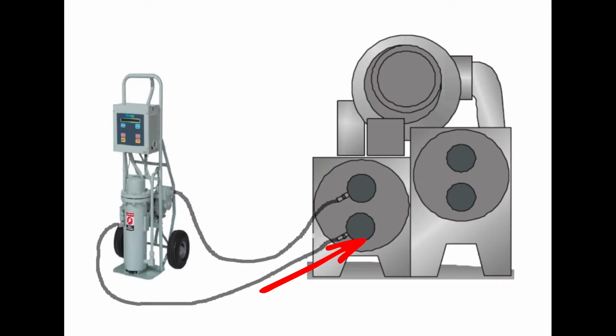Now, the point that causes me caution is that it bothers me messing with the chemical treatment, or potentially messing with it, by connecting to the evaporator side, because these are almost always going to be a closed loop. Whereas on the condenser side, at least we're dealing with more of an open loop, and we've got a chemical station that's constantly monitoring, replenishing and maintaining the water treatment on the condenser side. Whereas on the evaporator, on a lot of plants, especially smaller plants, you're not going to have that same chem feed on the evaporator side.